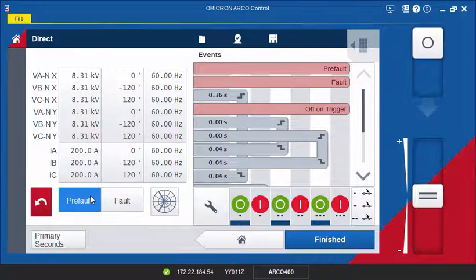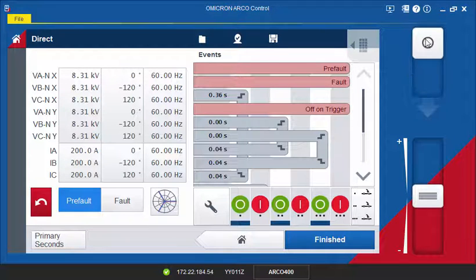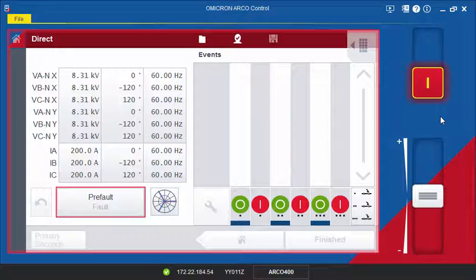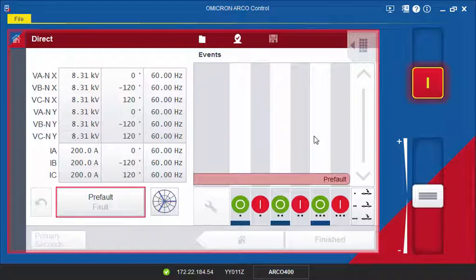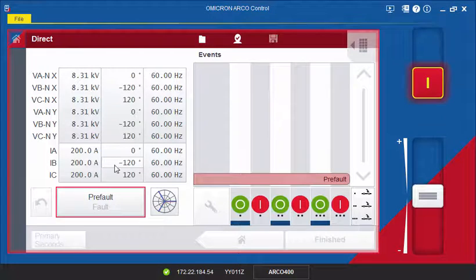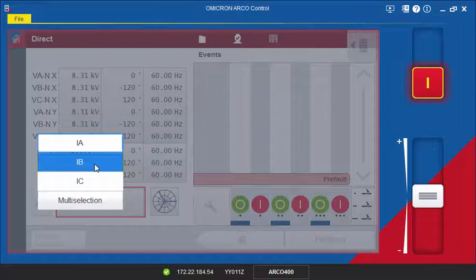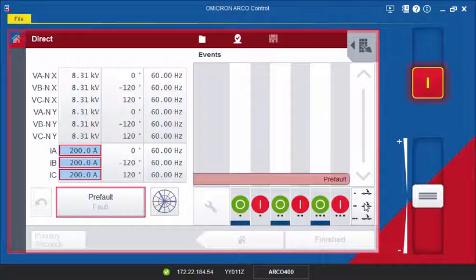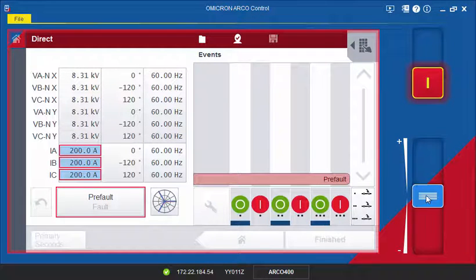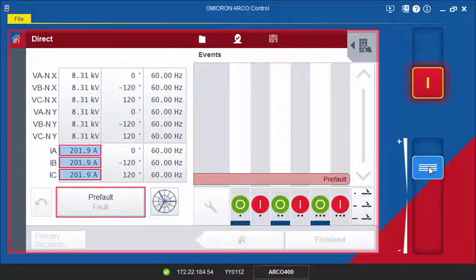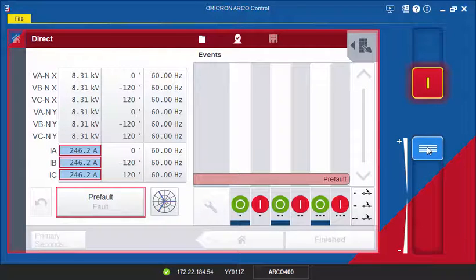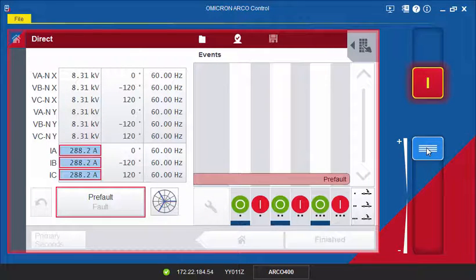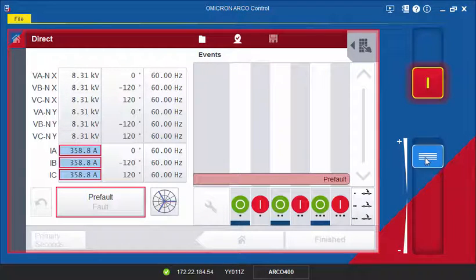You can also run a test using the pre-fault values and manually increase the values for the current outputs while the test is still running. You can increase the values until you receive the desired trip signal.